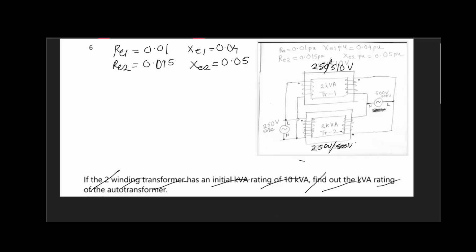So in the combination, a circulating current will flow through this, and the nature of that circulating current would be such that it strengthens the magnetic flux in the second transformer to cause a rise in its voltage, and has a demagnetizing effect on the first transformer.